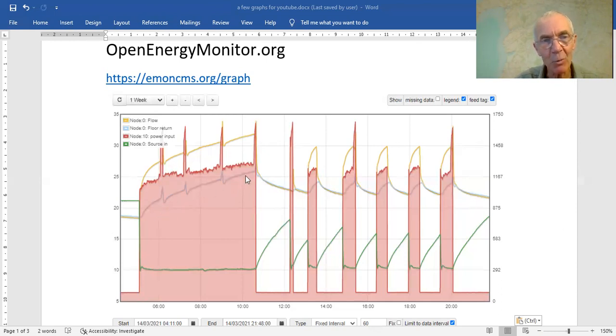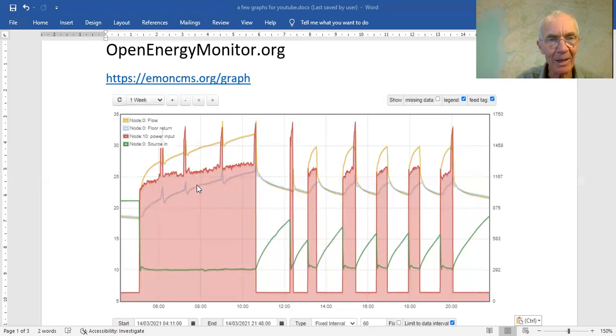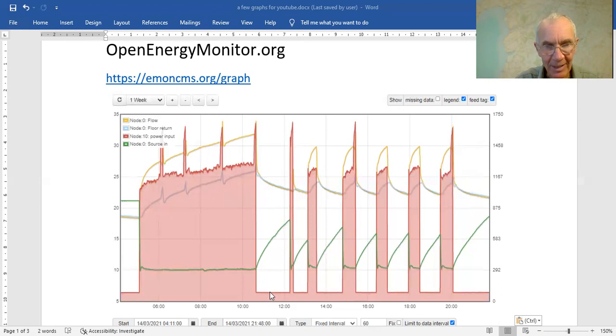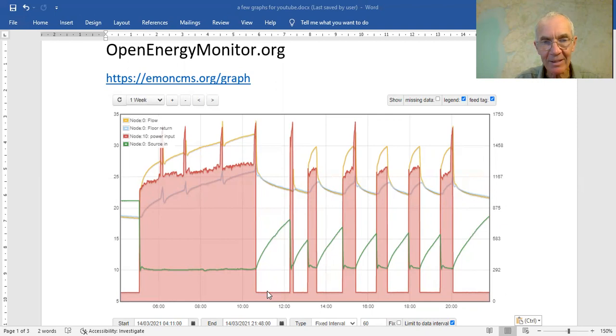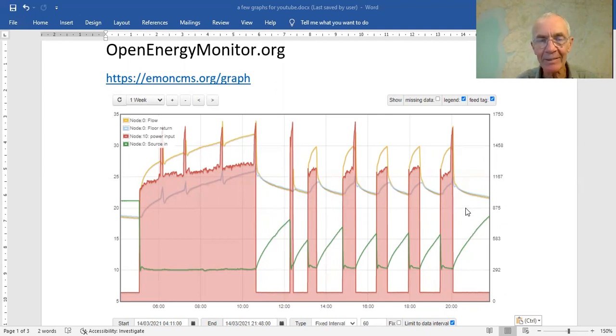When you have the return as well, you get two parallel lines. The difference between them is the temperature difference across the system, and by looking at that you can pretty well estimate what the flow rate is. As you can see here, they come together as you'd expect when the heat pump has gone off. You can look at standby power — or rather the pump overrun — and see if that's running when it should, or more than it should. Then there's a period of cycling on and off.